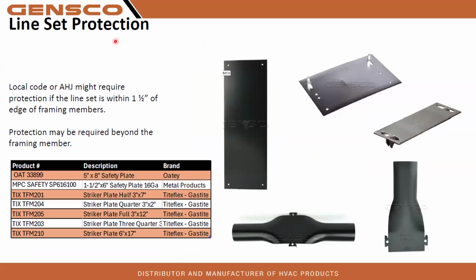Again, just bringing up here line set protection. Local code may require this. I think you guys have probably come across this before, right? Striker plates, right, to protect the line set within 1.5 inch edge of the framing member. So again, just listing some products there for that, if that's what you need to do, if code requires.